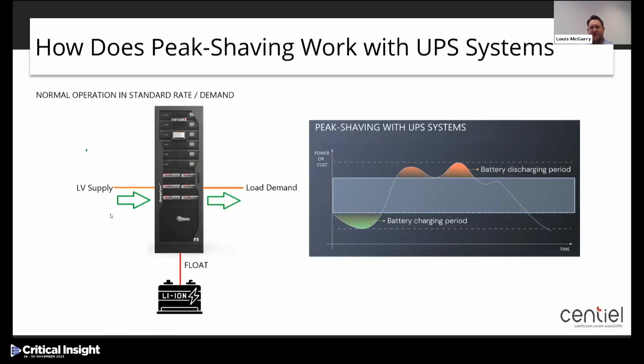So how does it work with the UPS? Well, when the energy cost or demand is at its lowest point, the UPS will operate in its normal mode, taking the required energy from the grid through its electronics and out to the load, whilst continuing to float charge its energy source or its battery bank. Note that the latest UPS systems should have efficiencies of 96 to 97% or greater across their load range when operating in true online double conversion mode.